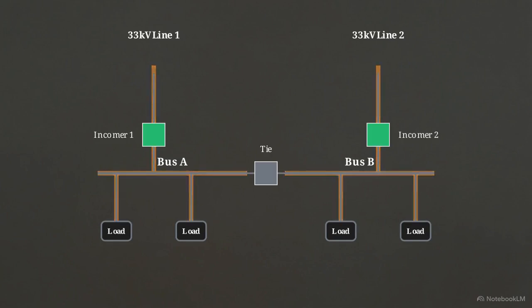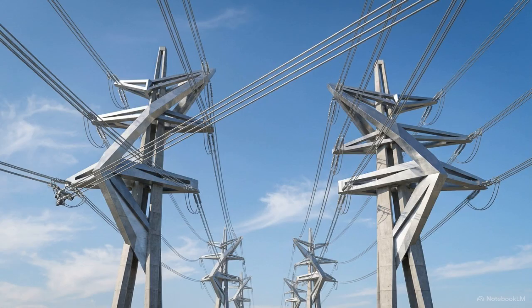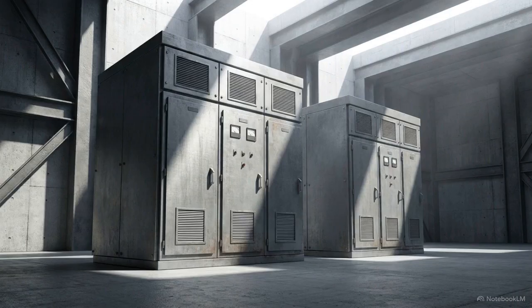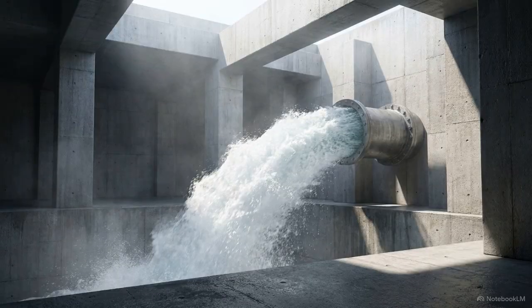Looking at this logic diagram, we see the facility's secondary selective topology. Two separate 33-kilovolt power lines feed the system. If one line fails, the central tie breaker mechanically closes, rerouting power from the surviving line to all essential equipment. Maintaining two independent transmission lines, dual incoming breakers, and a central bus coupler guarantees that a localized grid failure cannot interrupt the constant supply of raw water.